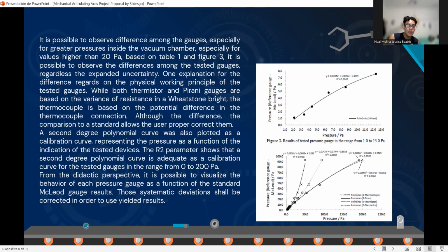A second degree polynomial curve was also plotted as a calibration curve, representing the pressure as a function. A second degree polynomial curve is adequate as a calibration curve for the test gauges in the range from 0 to 200 pascals. From this perspective, it is possible to visualize the behavior of each pressure gauge as a function of the standard McLeod gauge results. Those systematic deviations shall be corrected in order to use the yielded results.